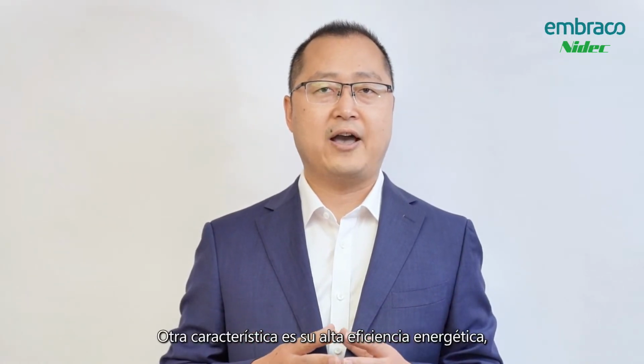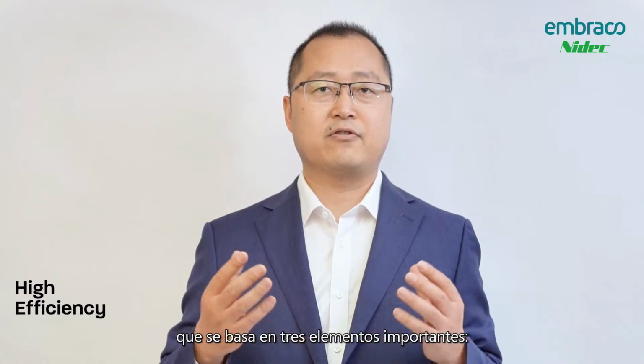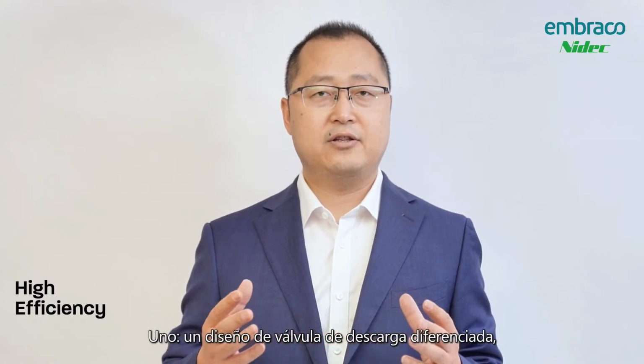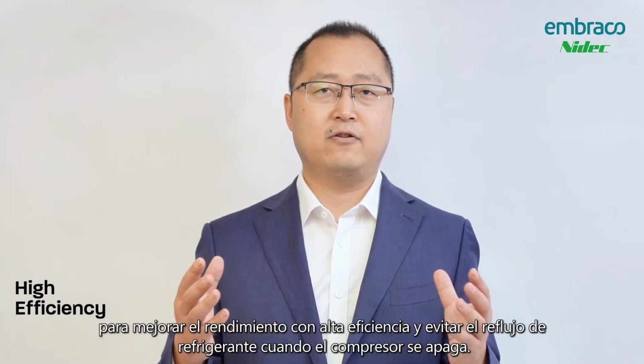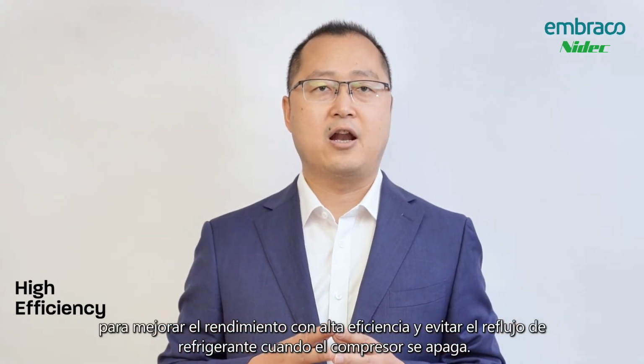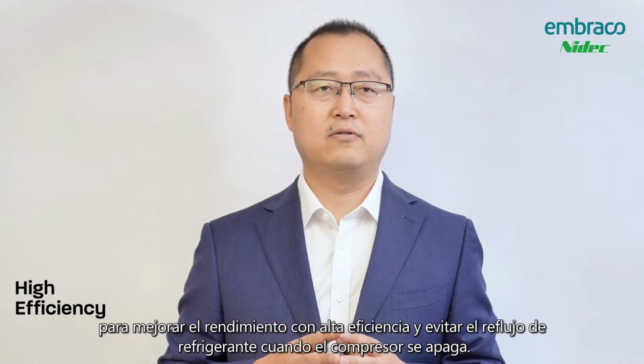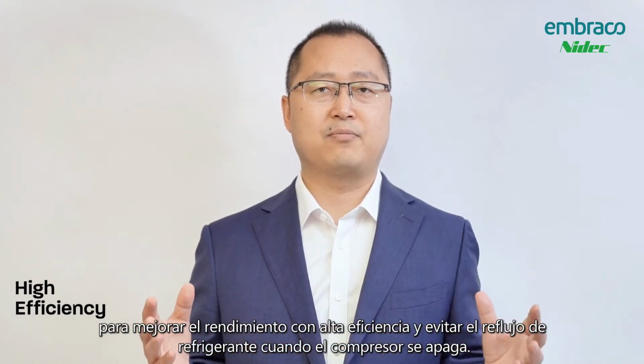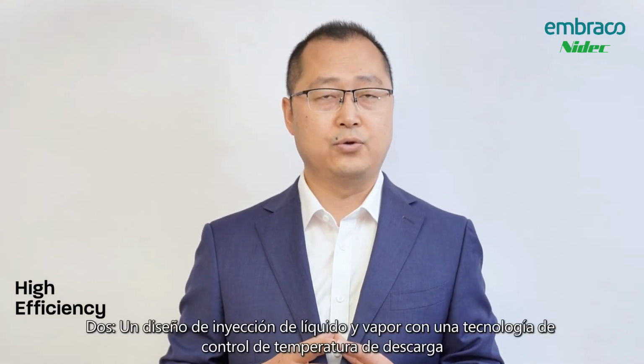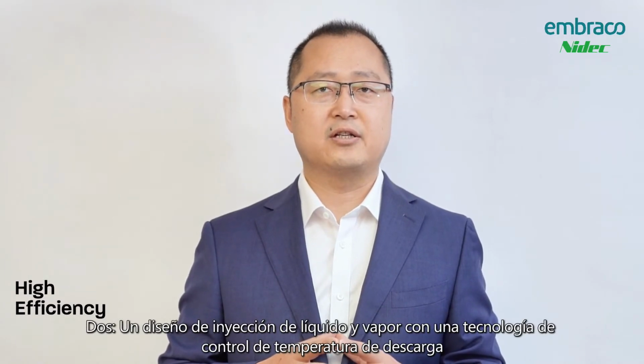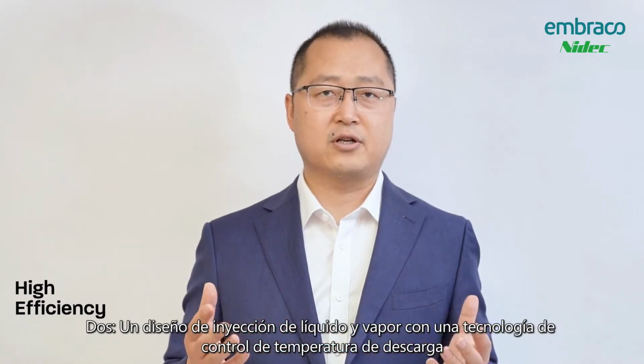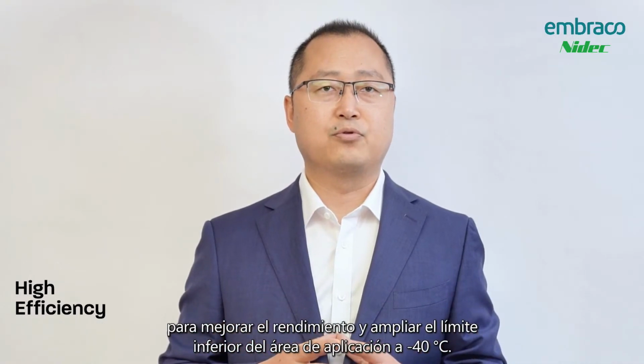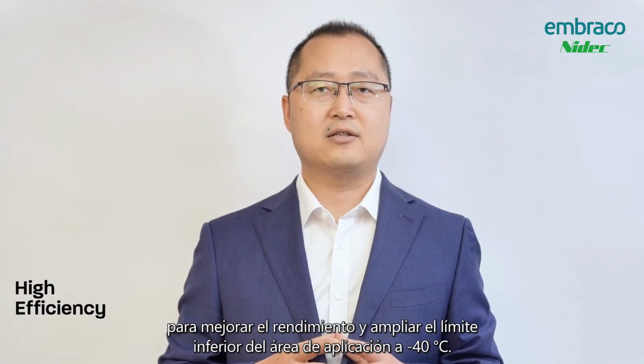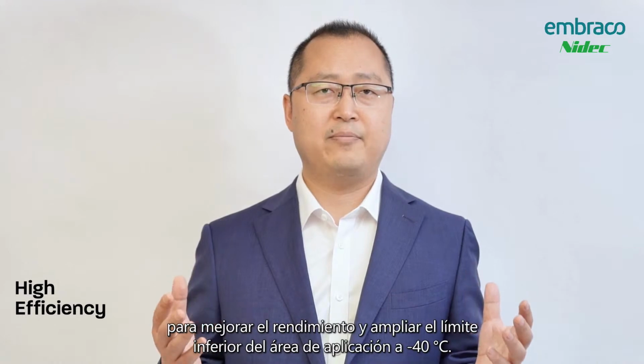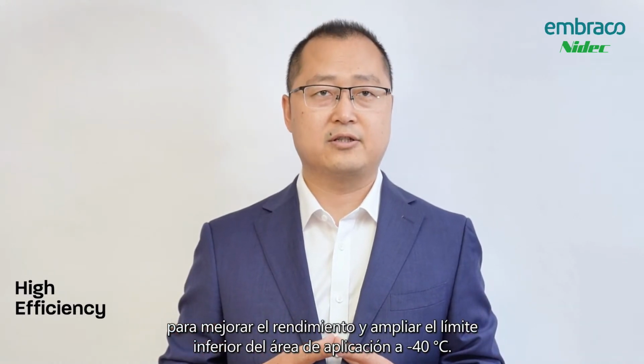Another feature is high energy efficiency. It comes from three important elements. One, a differentiated discharge valve design to improve performance with high efficiency and prevent the backward flow of refrigerant when the compressor shuts off. Two, a liquid and vapor injection design with discharge temperature control technology to improve performance and also enlarge the application envelope's lower limit to minus 40 Celsius.